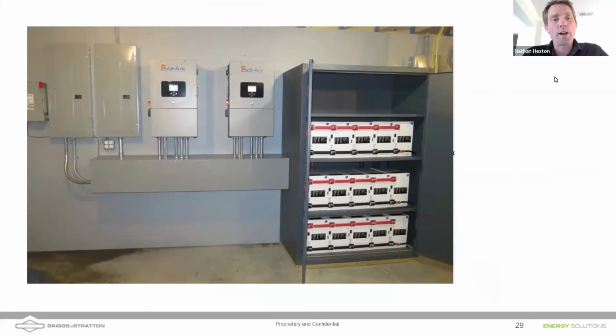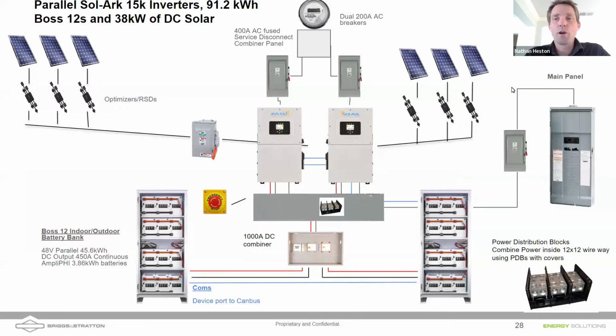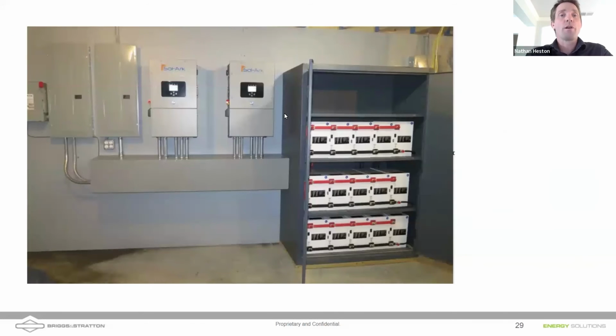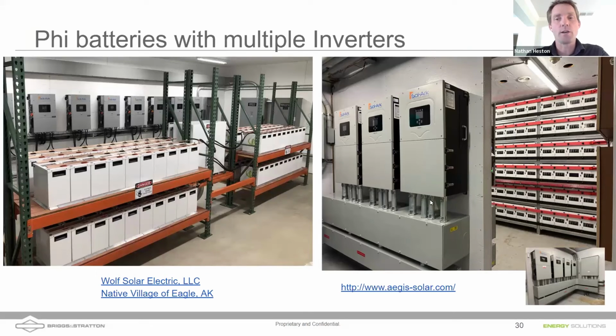And as well, using that wire way below, the Sol-Ark 12K used to have their air intake on the sides. I'll point out that the 15Ks have the air intake on the bottom, and so that means you can space these closely together. I believe, John, is it 6 inches between Sol-Ark 15Ks on the sides if you're paralleling them? Yeah, you want to have enough room to stick your hand in and be able to turn that solar disconnect on the side of the inverter, which gets you out of the need for an inline solar disconnect. But yeah, you do need to stick your hands in there.